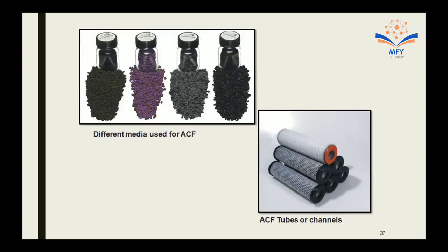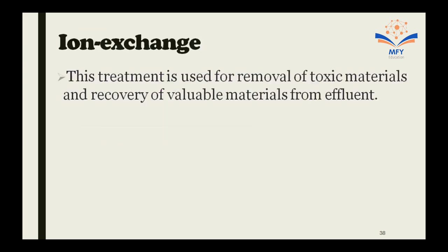Now these are different media used for activated carbon filters, activated carbon tubes or channels. And now the ion exchange. This treatment is used for removal of toxic material and recovery of valuable material from effluent. Ion exchange is only economical when recovered material is reused, so not economical when the objective is only removal of pollutant. Majorly used for recovery of chromium, nickel, phosphate and sulfuric acid, also copper, lead, mercury, and removal of cyanides from wastewater after chromium recovery.